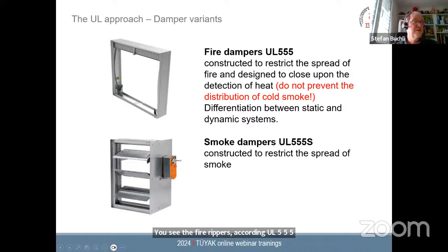Fire dampers are almost non-motorized. Very often they look like this. This is a so-called curtain damper. It's like a jalousie coming down here. There is a tripping device here, a mechanical part. If this part sees temperature, it just releases the shutter here, which falls down. This component is reacting very late in a fire unless you have very high temperatures from the beginning, which you seldom have actually. So it does not prevent the distribution of cold smoke in the initial phase of a fire. So people must be aware of that.